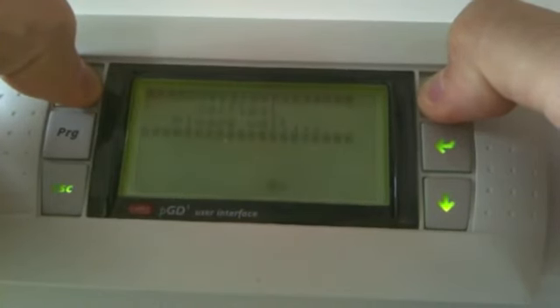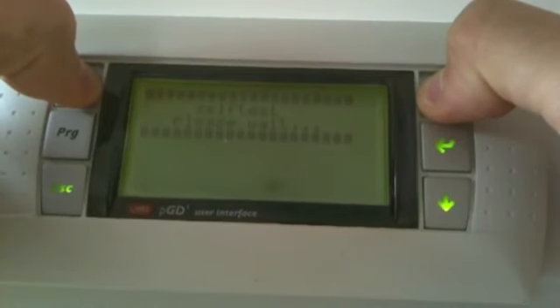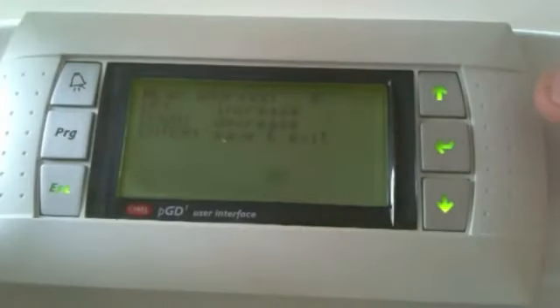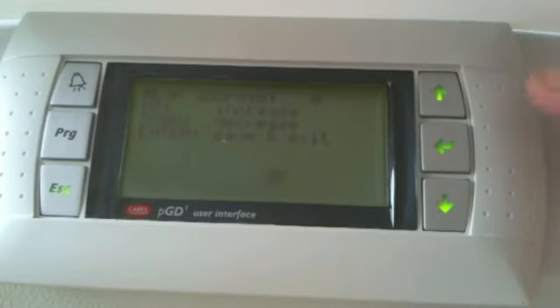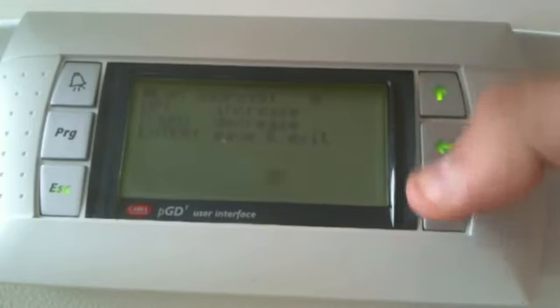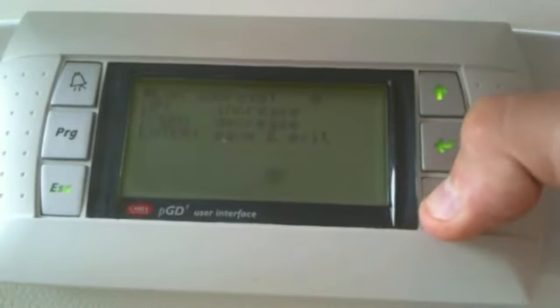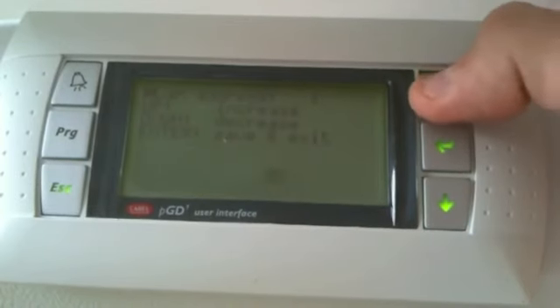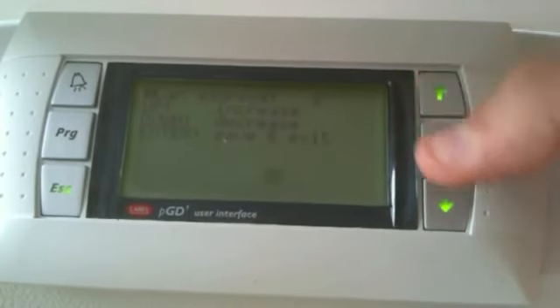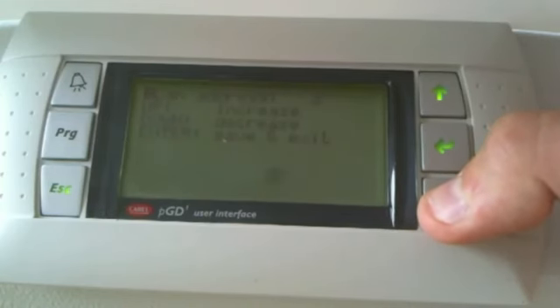The 'self-test please wait' screen will appear. You have to keep pressing the buttons until the following screen appears, then you can release your hands. You will see 'PLAN address 0' — this is the PLAN address of the controller. By pressing UP and DOWN (not ENTER) you can set the address of the controller to values 1, 2, 3, 4, up to 31.